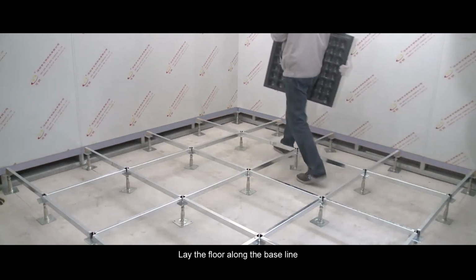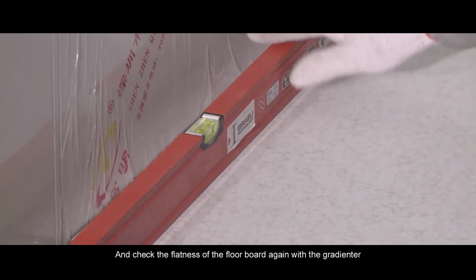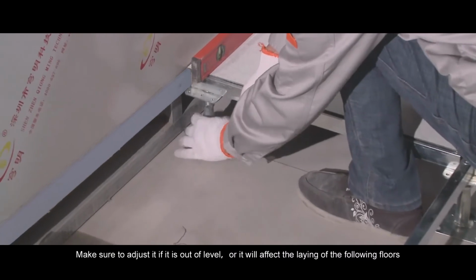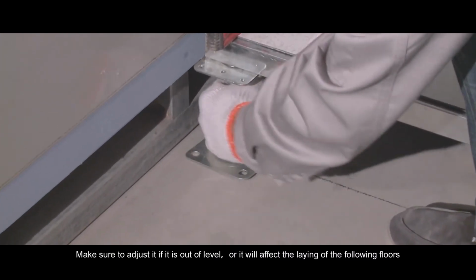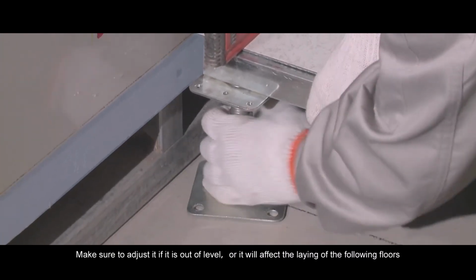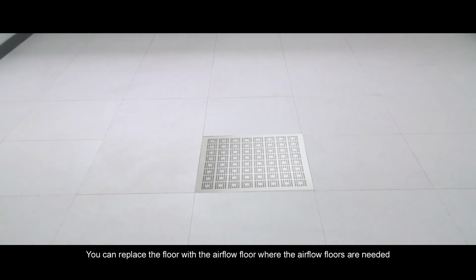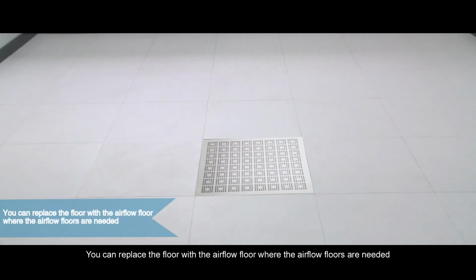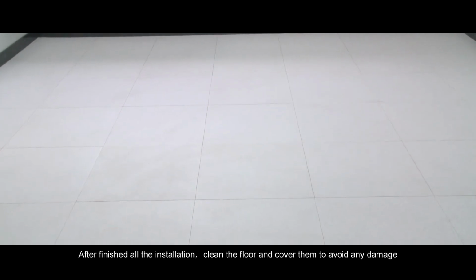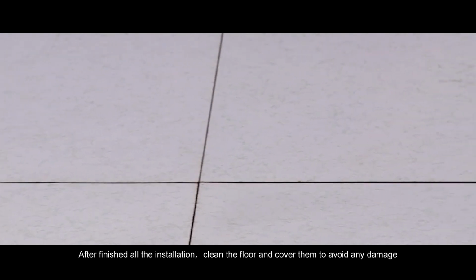Lay the floor along the baseline and check the flatness of the floorboard again with the gradienter. Make sure to adjust it if it is out of level, or it will affect the laying of the following floors. You can replace the floor with the airflow floor where the airflow floors are needed. After finished all the installation, clean the floor and cover them to avoid any damage.